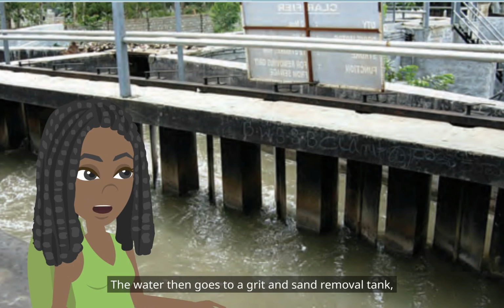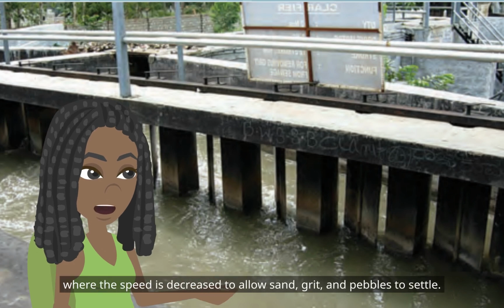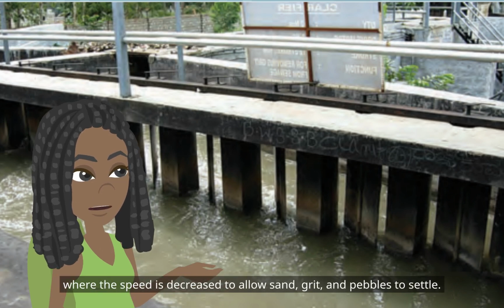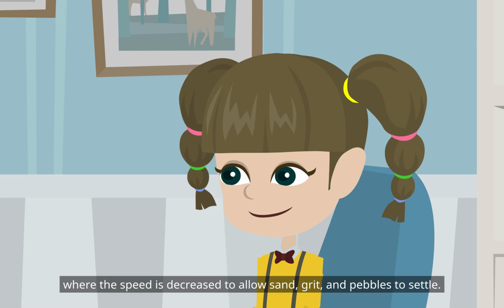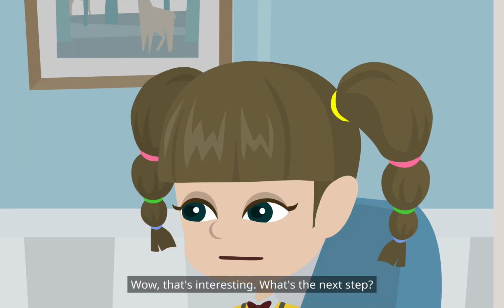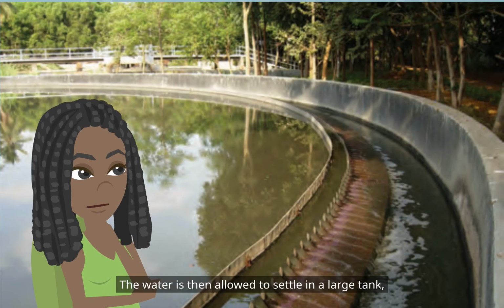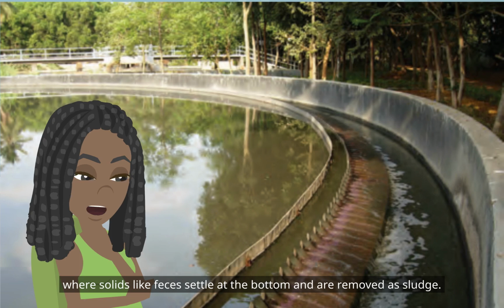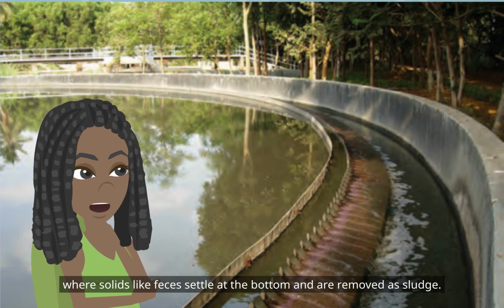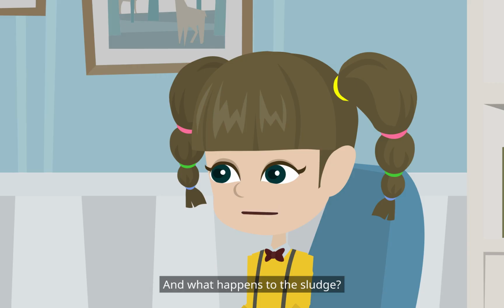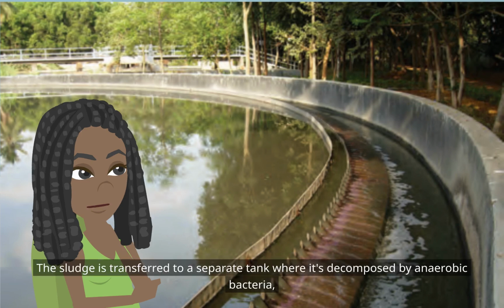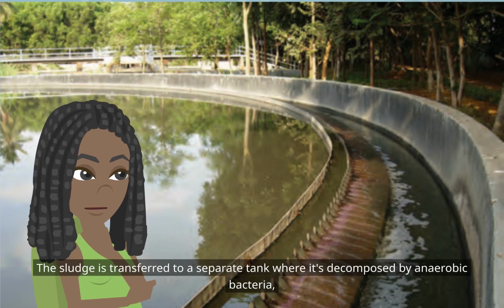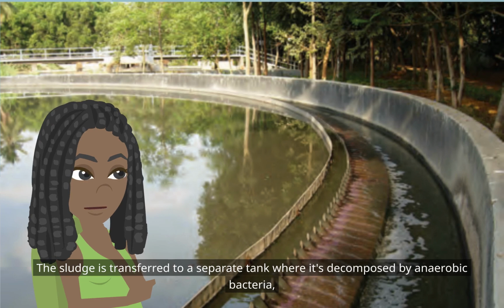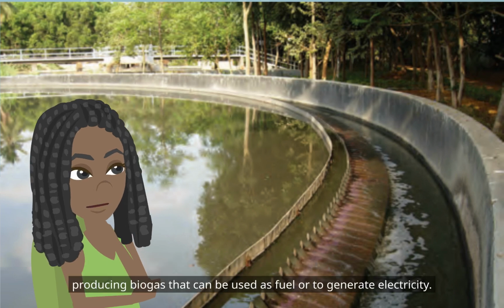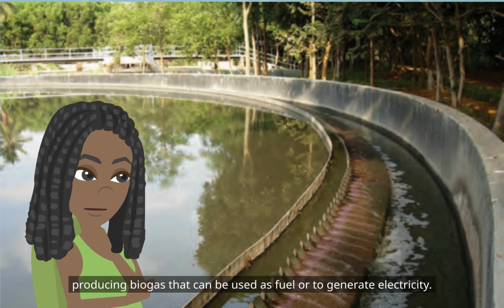The water then goes to a grit and sand removal tank, where the speed is decreased to allow sand, grit, and pebbles to settle. Wow, that's interesting. What's the next step? The water is then allowed to settle in a large tank, where solids like feces settle at the bottom and are removed as sludge. And what happens to the sludge? The sludge is transferred to a separate tank where it's decomposed by anaerobic bacteria, producing biogas that can be used as fuel or to generate electricity.